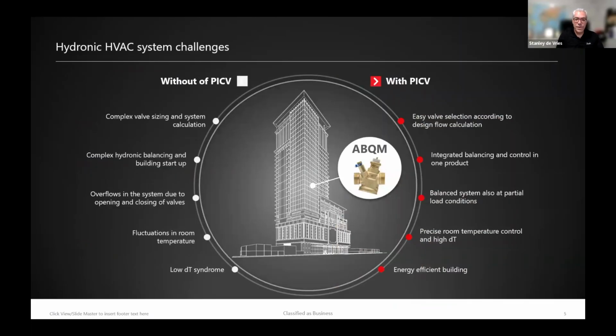As we mentioned also before, PICV, pressure independent control valve, has been an up and coming product where in many parts of the world this is a rather standard product already. I mean, Europe, basically Germany, England, pretty much standard. If you go to the Middle East, also Dubai, it's a standard product, and that is because it brings you quite a lot of benefits. So where before, for example, it was complicated to size the valves, control valves, if you go to PICV, it's very simple.